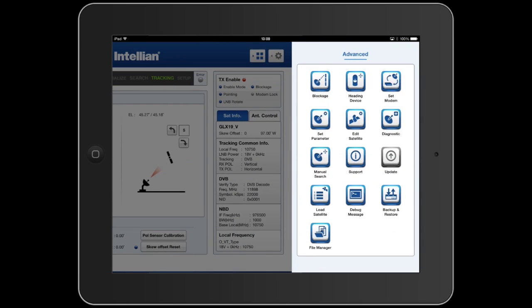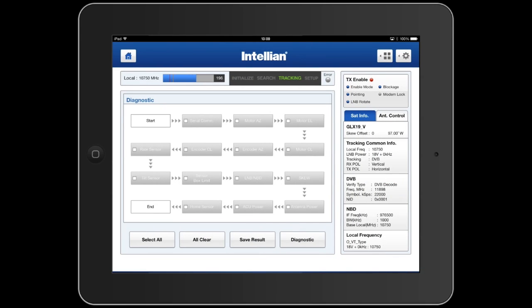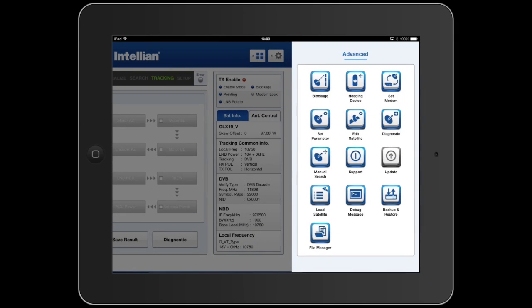The Aptus mobile app allows us to perform full diagnostic tests on the antenna. This diagnostic test allows us to select different tests to be performed, or we can select the complete test cycle. Once each test is selected, hitting the diagnostic key will allow the whole system to perform a diagnostic test. Once the test is complete, a log will be printed out.